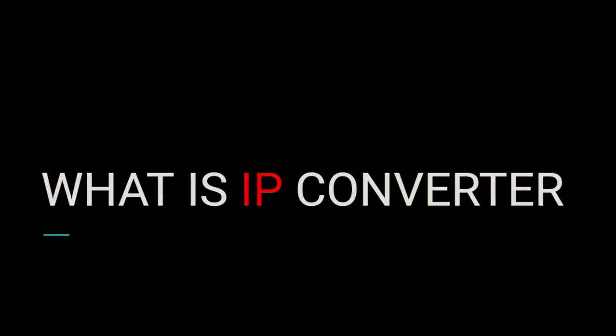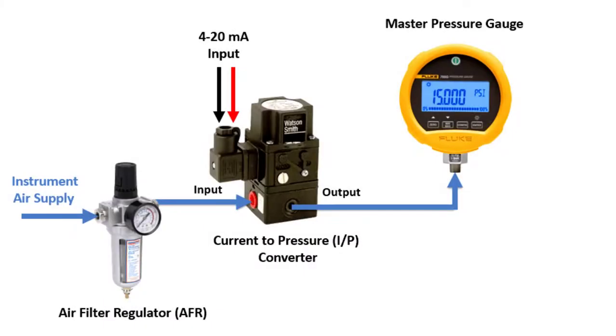Now let's check what is an IP converter. IP converter is a main part of a control valve. It will control the air supply from the compressor to the valve, proportional to the current feed.